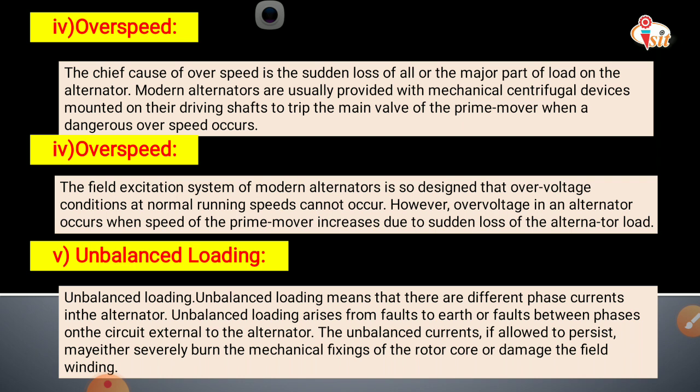Unbalanced loading means there are different phase currents in the alternator. Unbalanced loading arises from faults to earth or faults between phases on the circuit external to the alternator. If the unbalanced currents are allowed to persist, they will severely burn the mechanical fixings on the rotor core or damage the field winding.